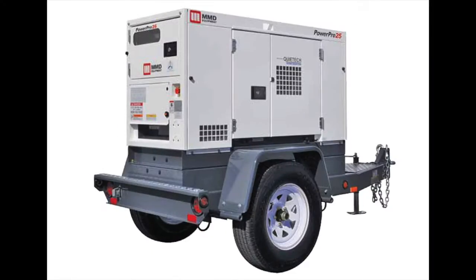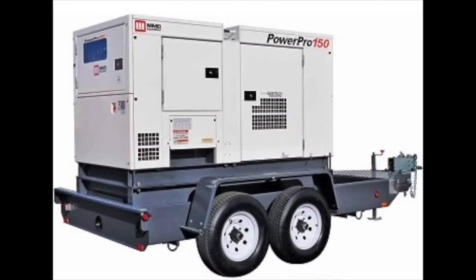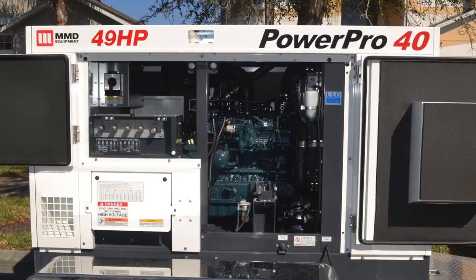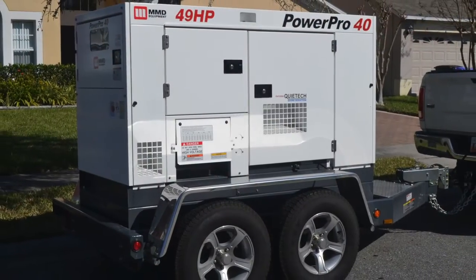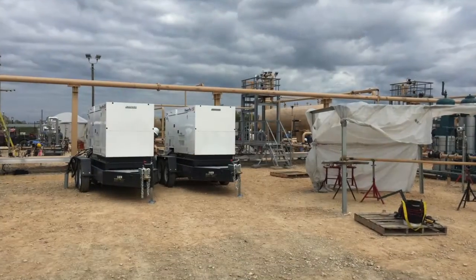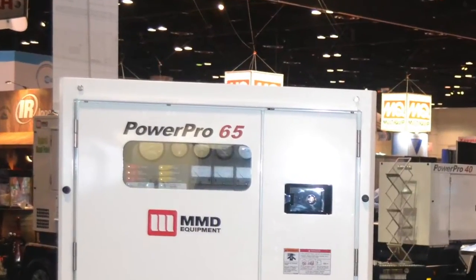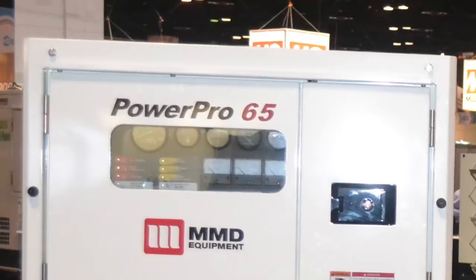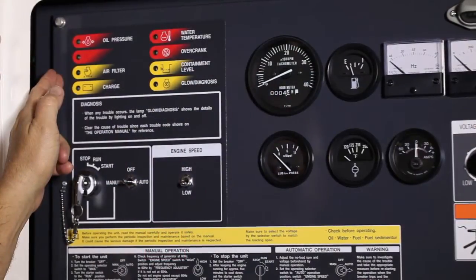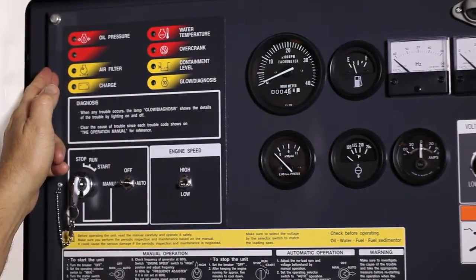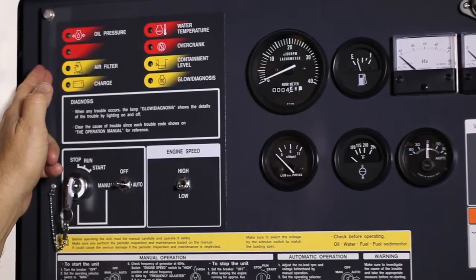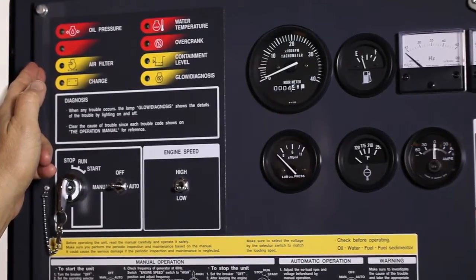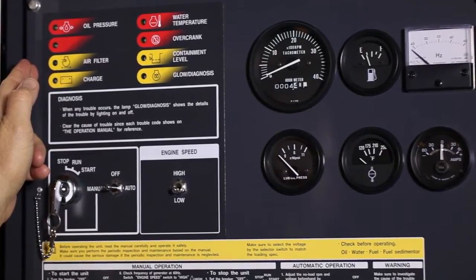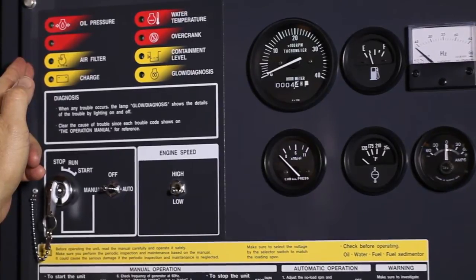With a range from 25 kVA up to 150 kVA, MMD generators can handle a variety of jobs from entertainment to industrial to oil and gas applications. Let's take a closer look at the MMD PowerPro. Starting at the back control panel, all MMD generators feature a direct diagnostic light system. Items highlighted in red are critical alerts. Items highlighted in yellow are for warning and information.